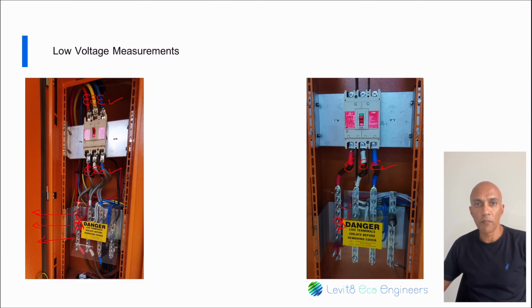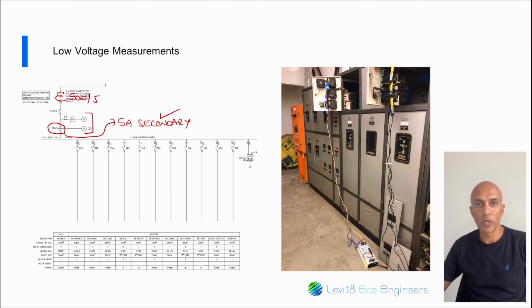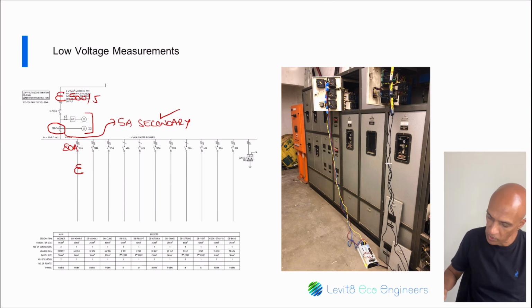If you want to measure the power on one of the feeders, you would have to use your own current clamps and ensure that the clamp's primary rating is more than the circuit rating. So here we go. If we want to measure the current on one of these feeders, then we would have to connect our CT onto this feeder. Now remember, just don't use too high a rating clamp.